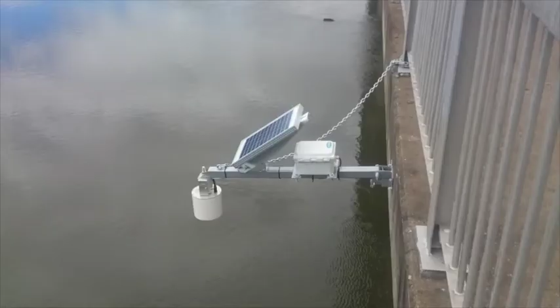Ultrasonic and radar type measurement. Ultrasonic and radar are non-contact type distance measurement sensors. The ultrasonic sensor measures the distance of target objects, here the water surface, by sending pulsed ultrasonic waves at the object and then measuring the time for the echo to return. Knowing the speed of the wave, the sensor can determine the distance of the object. Thus, it gives the distance between the sensor cone and the water surface.